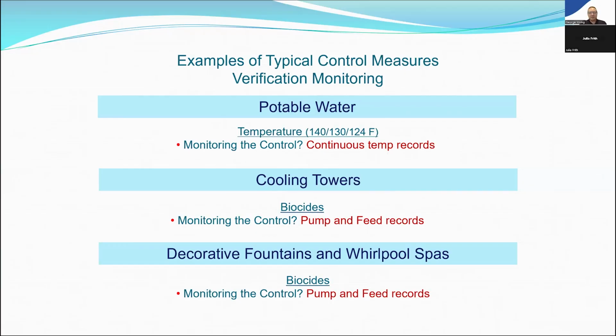Talked briefly about biocides and cooling towers, and how pump and feed records are the way that you understand that, okay, we are adding this biocide on this frequency as our control measure. Our verification is those pump records and feed records, and are we having that happen? Almost every single time I've had a previously negative cooling tower go positive, it's because of a pump failure. And they would have seen that with regular monitoring of that pump validity, whether it's an electronic notification that the pump is working, or it's a visual inspection that the pump is distributing as it should. Same thing with decorative fountains, whirlpool spas. The verification for that is going to be your pump and feed records of what type of biocide you have and how often they're going in.